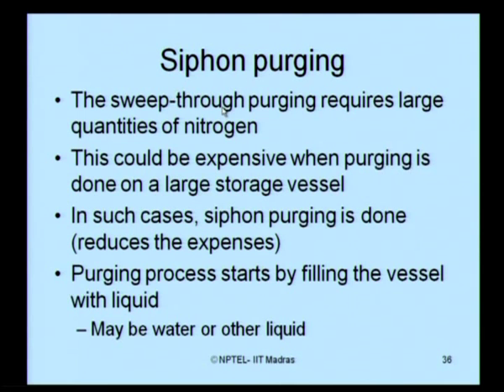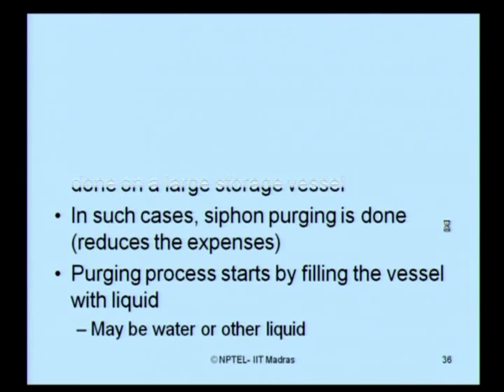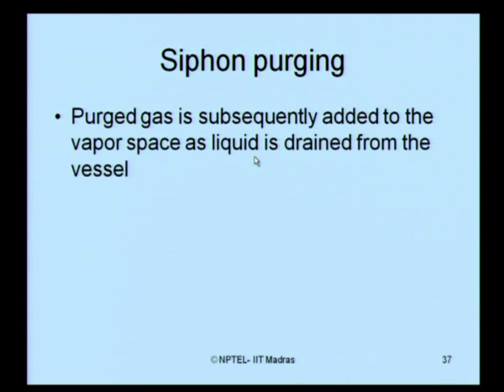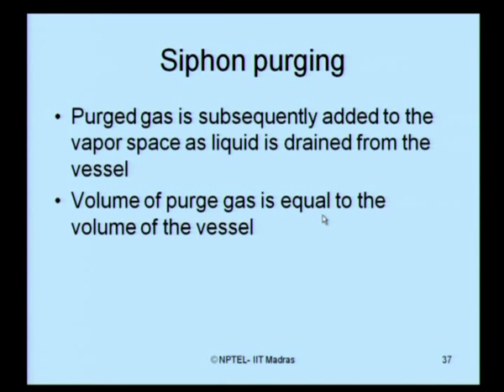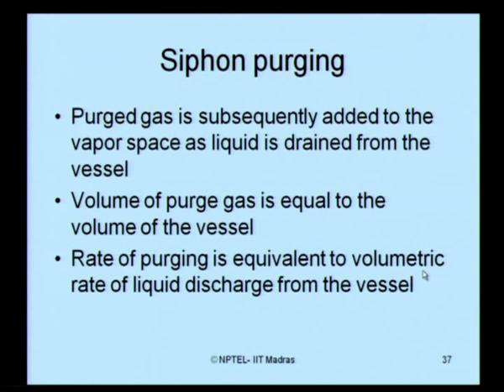For large storage vessels, siphon purging is used to reduce expenses. Siphon purging starts by filling the vessel with liquid — water or any other liquid. The purge gas is subsequently added to the vapor space as the liquid is drained off from the vessel. The volume of purge gas is exactly equal to the volume of the vessel, and the rate of purging equals the volumetric rate of liquid discharge. In the next class, we will discuss different methods where we can use flammability diagrams for explosion control models. Thank you.